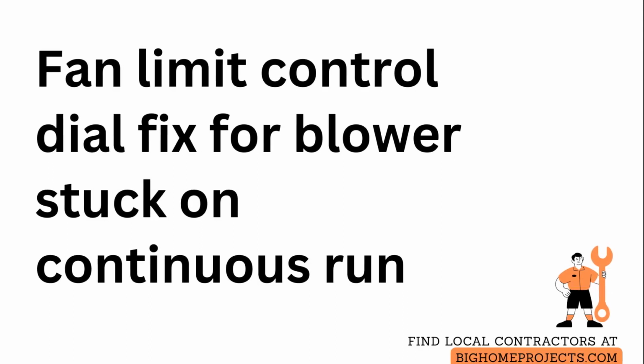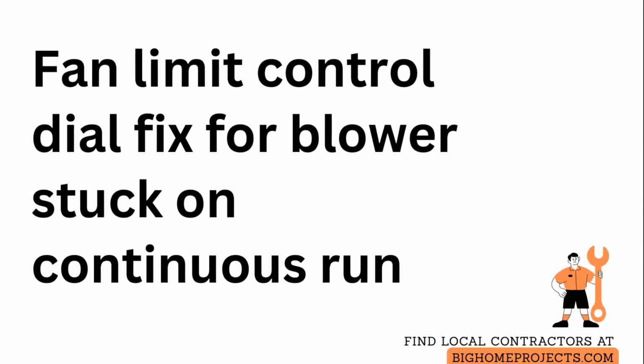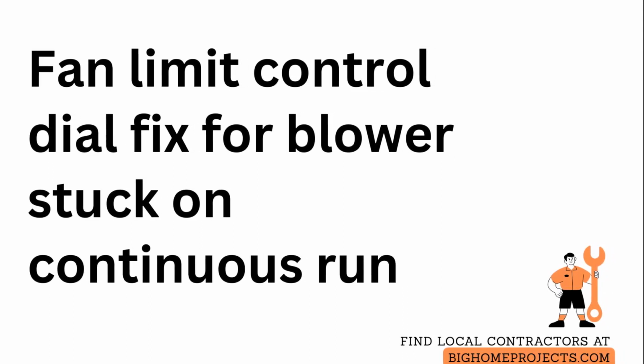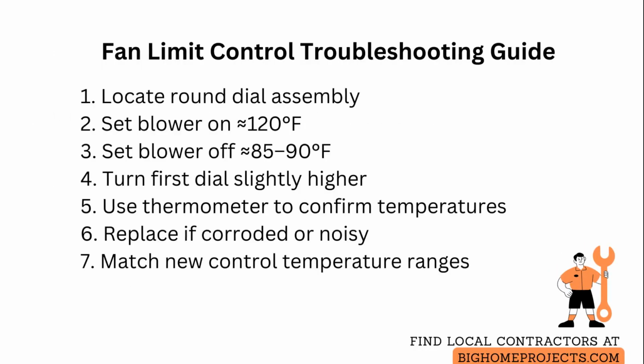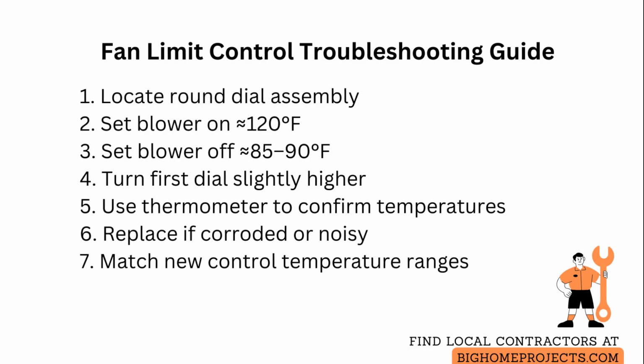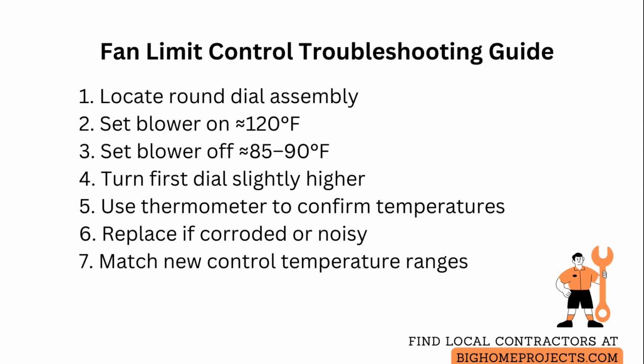If your fan limit control will not turn the blower off, address the dial settings and the device calibration first. The fan limit control senses temperature to command blower on and off and to protect the heat exchanger, so start by locating the round dial assembly on the furnace near the heat exchanger.